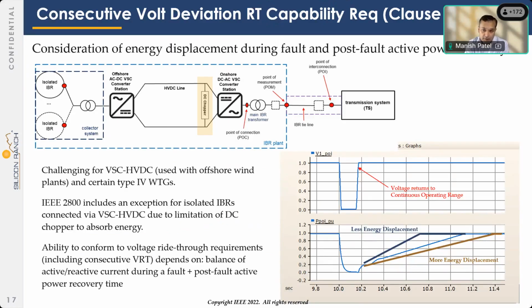Consideration of energy displacement during fault and post-fault active power recovery. I feel we could have written not only a consecutive voltage dip requirement, but even a voltage ride-through requirement that was somehow tied to energy displacement. Because I don't think this is only an issue during consecutive voltage deviations. It might also be a real thing for some IBRs, if not all, some types of IBRs, even for one voltage dip of extended duration, right?